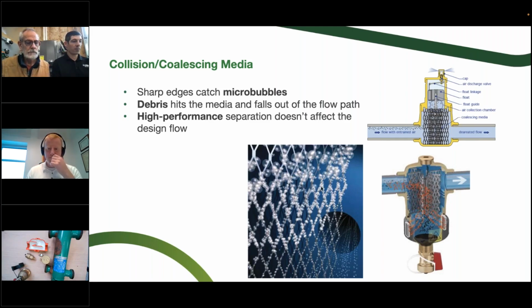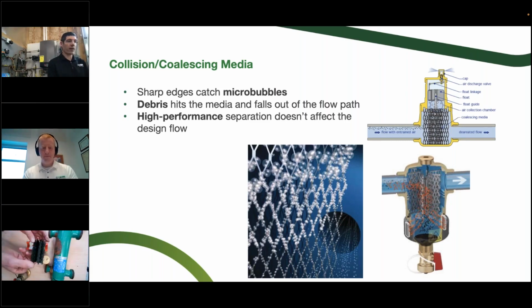So basically, with these sharp knife edges of this polymer collision media in the stream, it's going to gather the bubbles, and as soon as they get to a bigger bubble size, they can go up and out the top. And we'll cover what those different categories of air are in a second as well. But that's the collision media right there, if you haven't ever taken one apart. It's just a lot of sharp edges, like an eddy in a river, that catch and swirl and gather the bubbles, and then they float up and out the top. Same thing, we flip it over and it's a dirt separator, where particles collide and fall to the bottom, which we'll cover a little bit more.